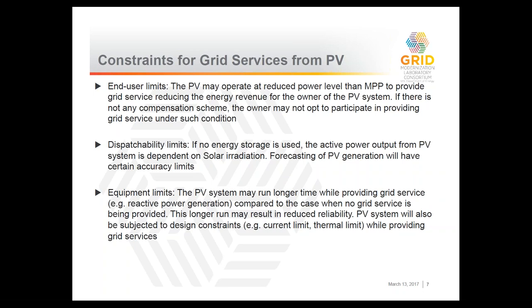Now, obviously, there will be constraints. When you are supplying grid services from PV, one of the big concerns will be the end-user limit. The PV may operate at a reduced power level relative to MPP to provide grid service, reducing the energy revenue. So if there is no compensation scheme, the owner may not opt to participate in such services.